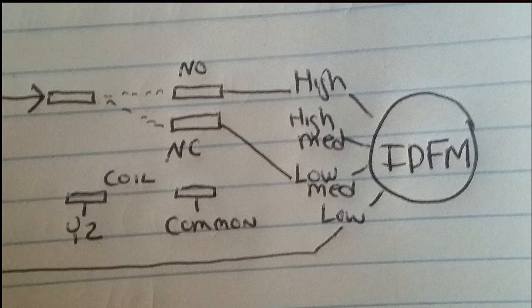If you have a 2-speed motor, you might have to do a little bit more figuring because you're going to be using the heat speed for two different things. So we're going to use a motor that has enough taps to produce a heating, cooling 1 and cooling 2, or cooling low and cooling high. If we look back at the relay, we are normally closed between the cooling tap and it goes directly to low medium. That's going to be our first stage of cooling.